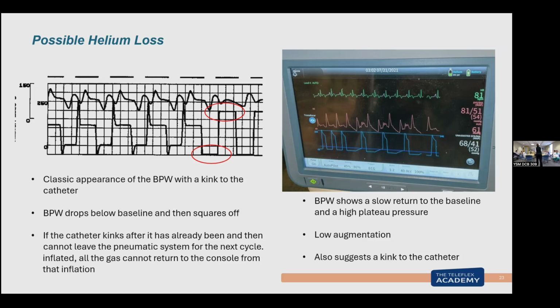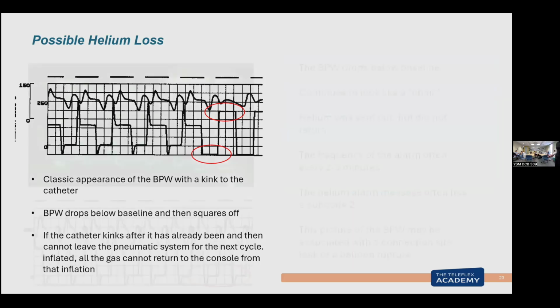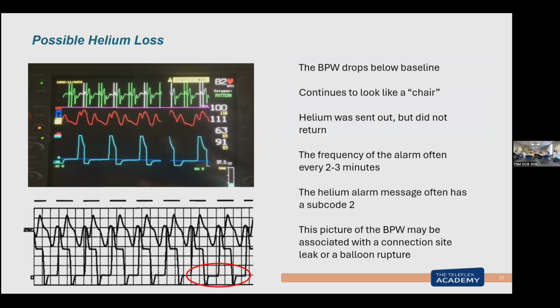And people think, why is this alarming? I don't see any blood in the tubing. He's not tachycardic. He's paralyzed. He's not moving. Why is he getting this alarm? Because the pump can see a problem. And that one would be a helium loss, subcode 2, like this one. It's not getting back to 0, it's just barely below. And so the pump will refill once.